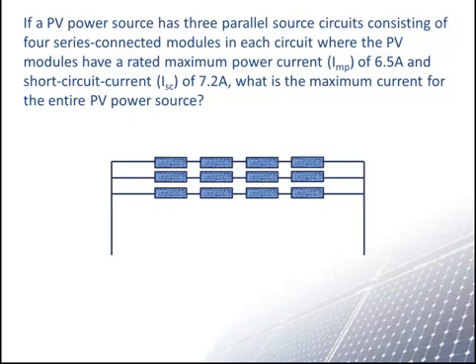The first thing to do here is to find the current for each string. Since each string has only series connected modules, the current for each string is that of just one module. NEC 690.8(A)(1) tells us that the maximum photovoltaic source circuit current is calculated as the module rated short circuit current multiplied by 125%. Multiplying the 7.2 amps times 1.25 gives a maximum source circuit current of 9 amps.